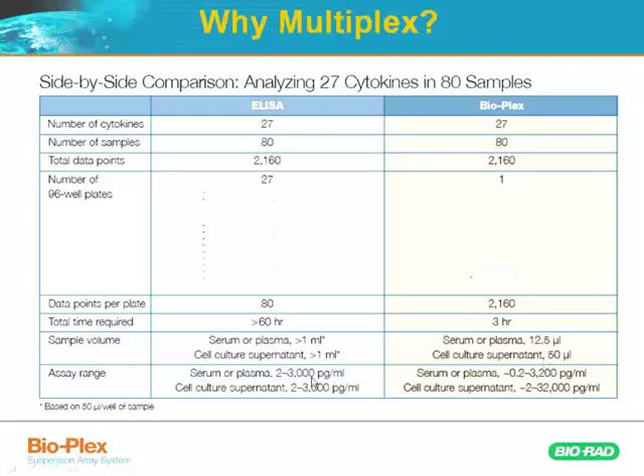If we compare assay range for serum or plasma, BioPlex is typically about tenfold more sensitive, down to 0.2 picograms per milliliter at the lower end, with the upper end about the same as ELISA. For other types of assays it's a similar range of detection, but again with a broader dynamic range with BioPlex.